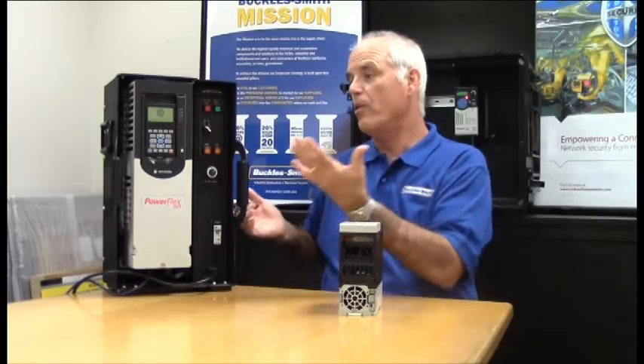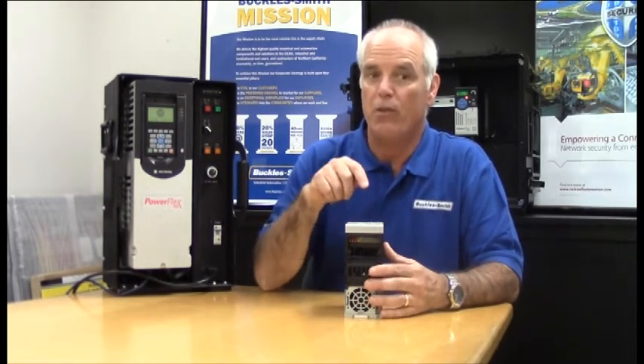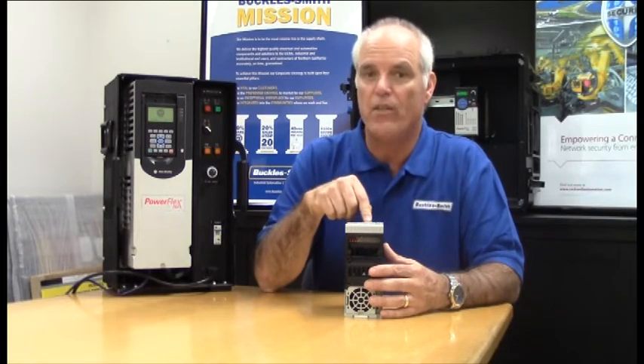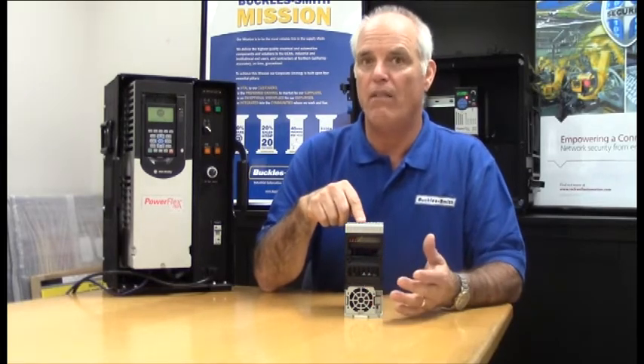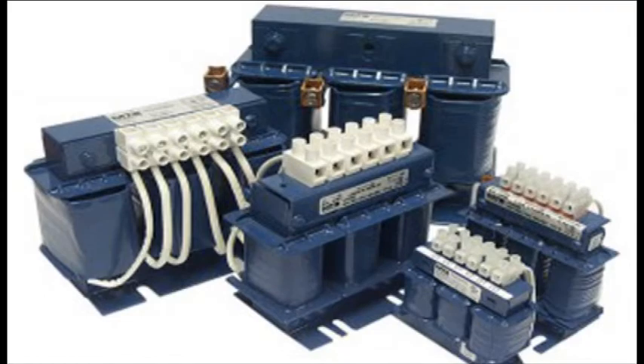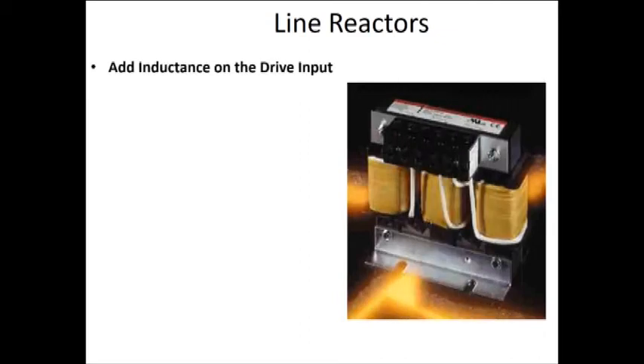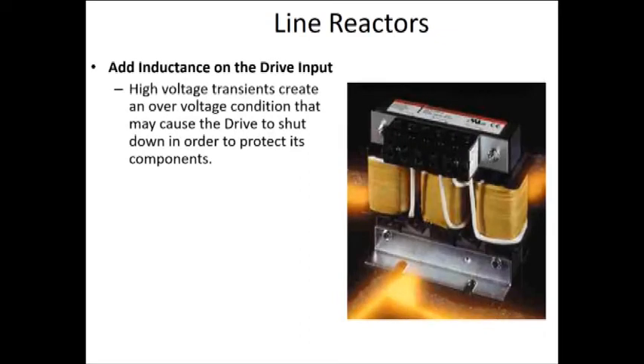How can you protect your important investment? Well, in the fine print of every drive manufacturer's manual, you'll see a recommendation that if your facility's transformer is greater than 10 times the kVA of the drive, you should use some form of external input protection, usually a line reactor. A line reactor is nothing more than an inductor that absorbs a portion of these transients, slowing the rise time of the spike and keeping the drive behind it safe.